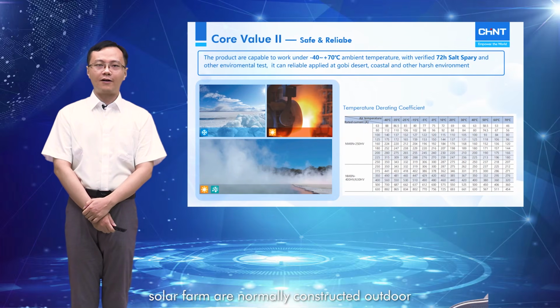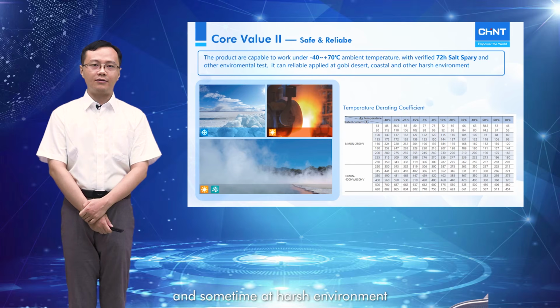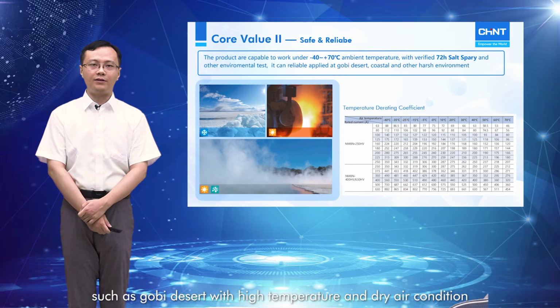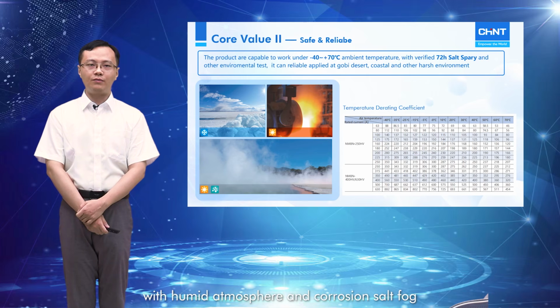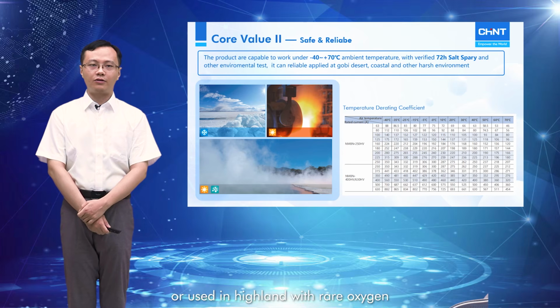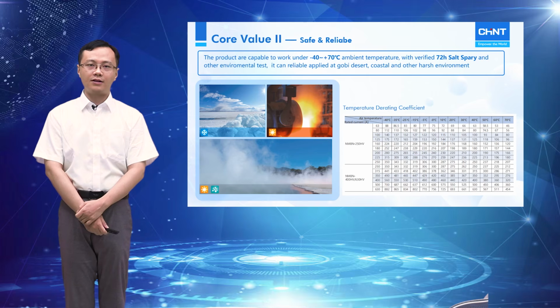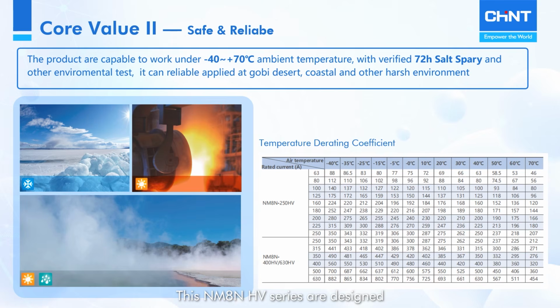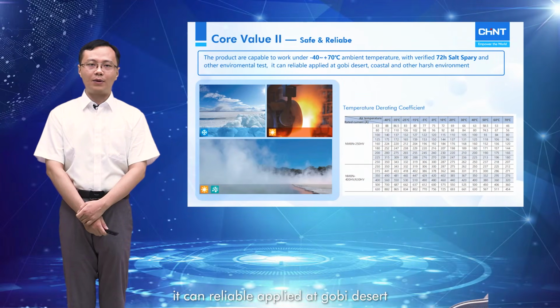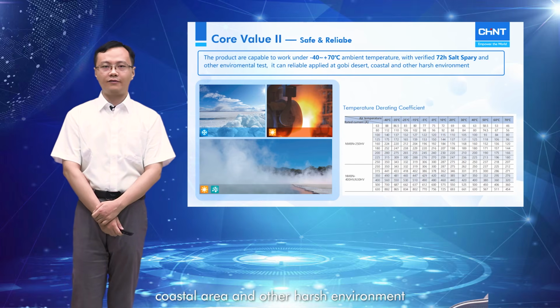Okay, as you may know, solar farms are normally constructed outdoors and sometimes in harsh environments such as the Gobi Desert with high temperature and dry air conditions, or sometimes in coastal areas with humid atmosphere and corrosive salt fog, or used in a highland with rare oxygen. This NM8N HV series is designed by fully considering these situations. It is capable of working under -40 to +70 Celsius degrees of ambient temperature. Besides, it features verified 72-hour salt spray and other environmental tests. It can be reliably applied in the Gobi Desert, coastal areas, and other harsh environments.